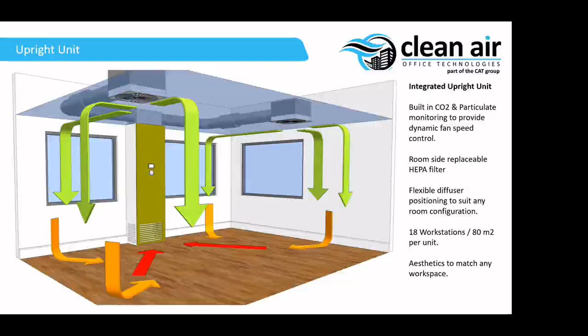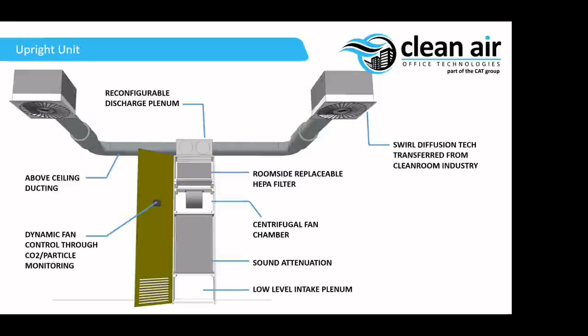So it's just a further view showing what's going on inside of it. This would be a locked up cabinet, so it can't be tampered with, but when the validation engineer comes round, they can open it up, check the fans are running correctly, directly test the HEPA filter, which is mounted at about eye level, and do the air change rates and issue a certificate against it.